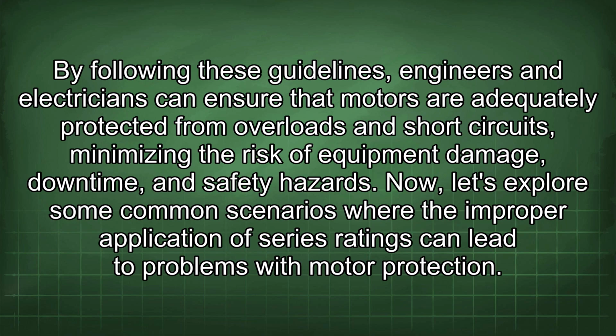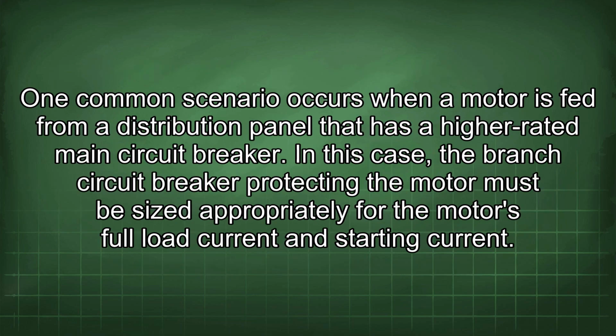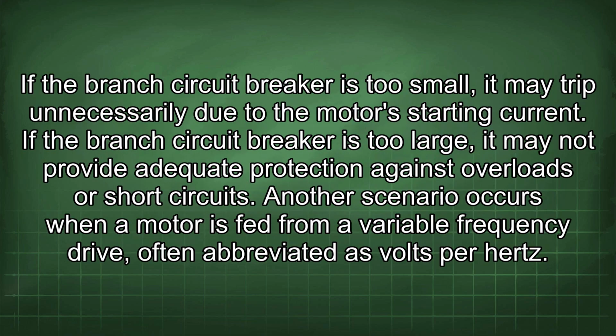Now, let's explore some common scenarios where the improper application of series ratings can lead to problems with motor protection. One common scenario occurs when a motor is fed from a distribution panel that has a higher rated main circuit breaker. In this case, the branch circuit breaker protecting the motor must be sized appropriately for the motor's full load current and starting current. If the branch circuit breaker is too small, it may trip unnecessarily due to the motor's starting current. If the branch circuit breaker is too large, it may not provide adequate protection against overloads or short circuits.